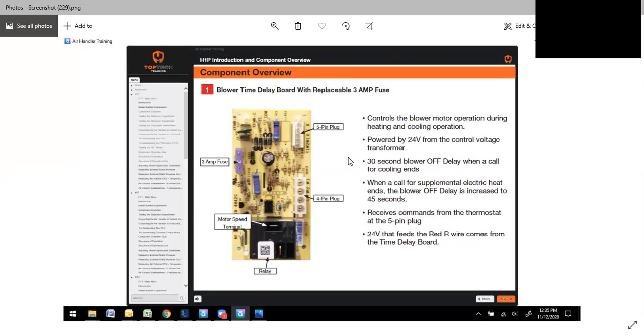This little board here controls the blower motor during operation in both heating and cooling. It's powered by your 24-volt transformer. It has a built-in 30-second blower off delay when cooling ends. When a call for supplemental extra heat ends, the blower off delay is increased to 45 seconds. It receives commands from the thermostat at the 5-pin connection right here. That's where your pigtails are. And the 24 volt that feeds the R comes from the time delay board. The 4-pin here is going to be for our auxiliary heat.